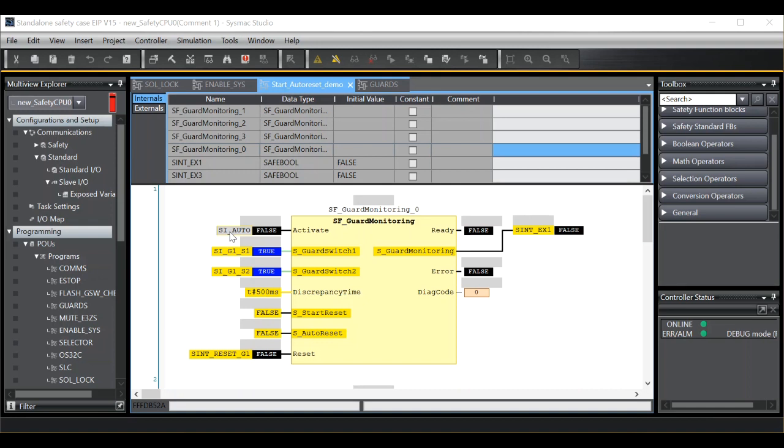If I activate the function block, you can see the output has stayed at false. If I now push reset, the output changes state. If I open and close the guard, another manual reset is required.